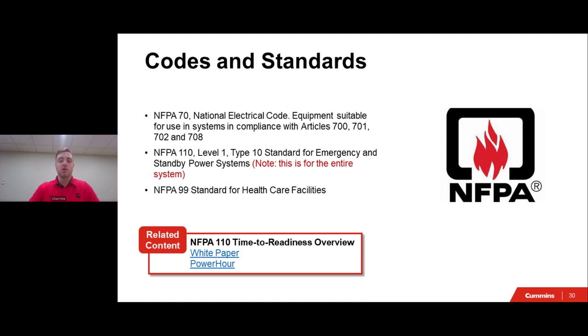So the first code, like I mentioned, is going to be NFPA, and most notably NFPA 70 at the top of this slide here, or NEC. So when looking into NEC, it is important to focus in on Articles 700, 701, 702, and 708. These will help guide you into understanding what is required of you based on what type of system you have. So understanding if you have a legally required, optional, or critical operations power system. So that's like what I talked about in the middle of this presentation. So if you want to know truly what your system is and what is needed of you and your system, take a look into those articles of NFPA 70 or NEC to get a better understanding of what you need to look for.